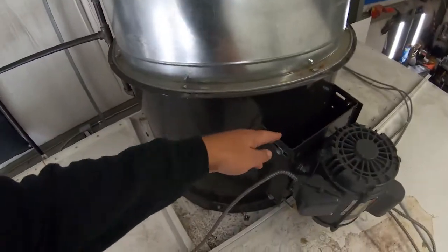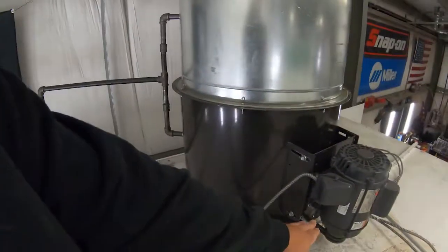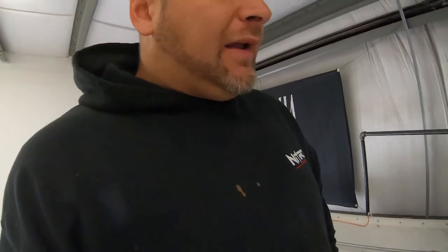Now, you could modify it, but honestly, it's not really gonna keep dust out. Dust is still gonna get in there. It's more just to keep debris out, or I mean, there's nothing gonna be up here. No one's gonna be up here. If you're up here, chances are you're gonna flip the service switch, flip a breaker before you service those belts anyway. And it's just more stuff to take off. So honestly, guys, I don't really see the purpose of putting that belt cover on. So I'm just gonna skip it. I am gonna keep it just in case I ever decide that I want to.